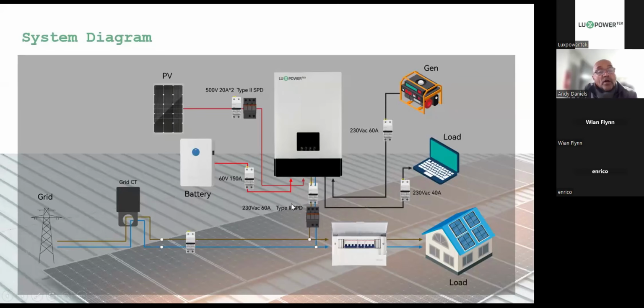The reason we ask for 60 amps is because you must remember that this machine and all of our machines have a bypass relay in there, which means that the power can come in through the machine without going through the inversion, and it'll bypass directly to load. So it means that you can exceed the capacity of 6 kilowatts on this machine on bypass current, right? So we'll go through the specification on that a little bit later.